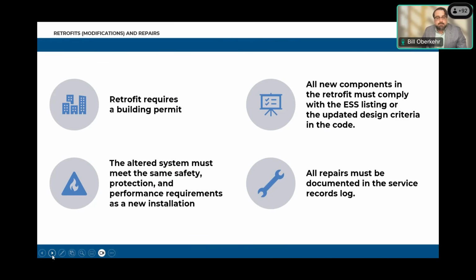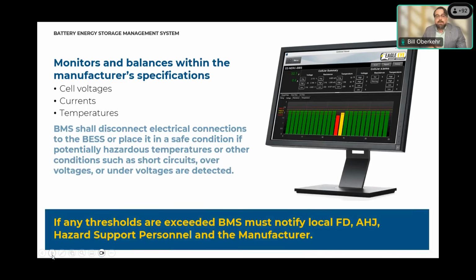We went through a little about the battery management system, but this is considered an instrumental safety feature in the energy storage system. It should be considered the eyes and ears of the battery system's health. The device constantly monitors the state of health of the energy storage system, and if the BMS were to fail, you're losing a critical safety feature. So in NYSERDA's own review rubric, this is one of our critical failures if there's anything wrong with the BMS.